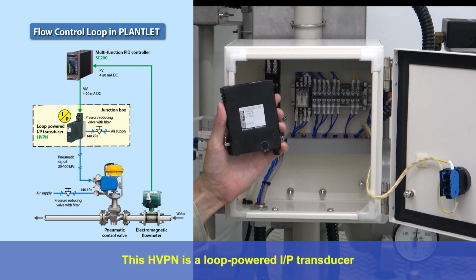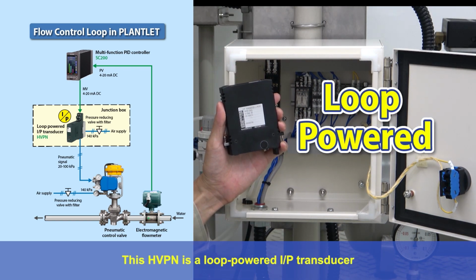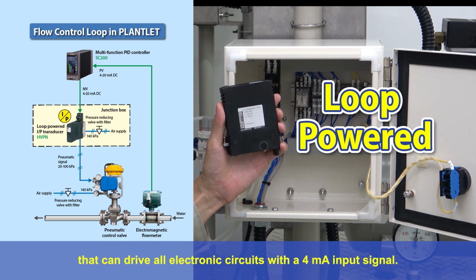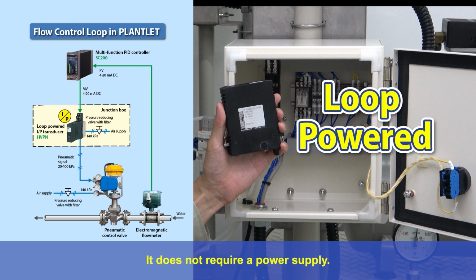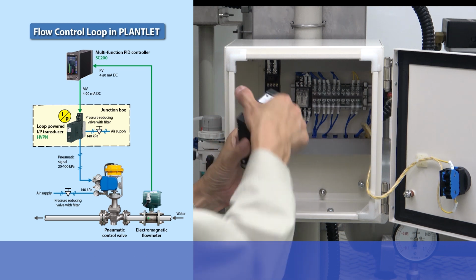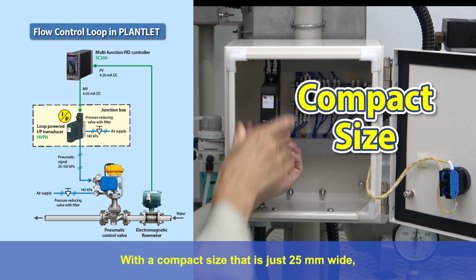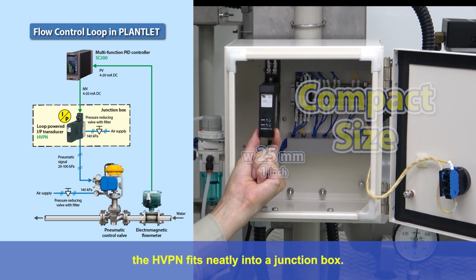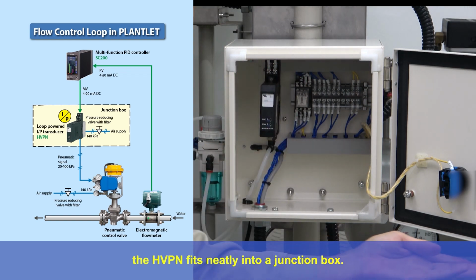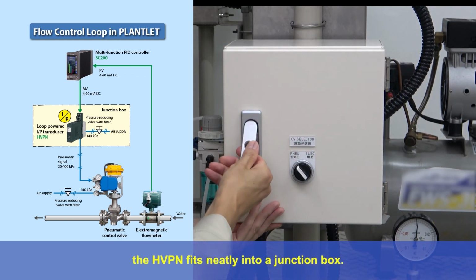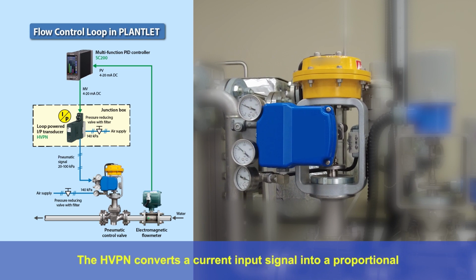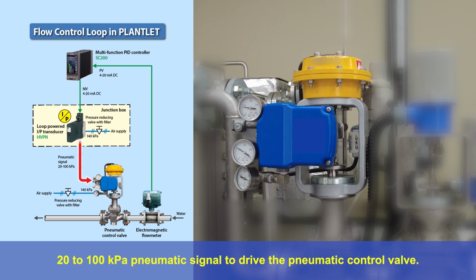This HVPN is a loop-powered I-to-P transducer that can drive all electronic circuits with a 4 milliampere input signal. It does not require a power supply. With a compact size that is just 25 millimeters wide, the HVPN fits neatly into a junction box. The HVPN converts a current input signal into a proportional 20 to 100 kilopascal pneumatic signal to drive the pneumatic control valve.